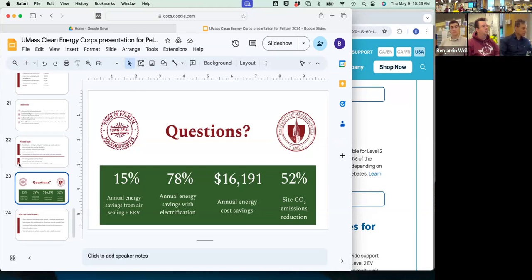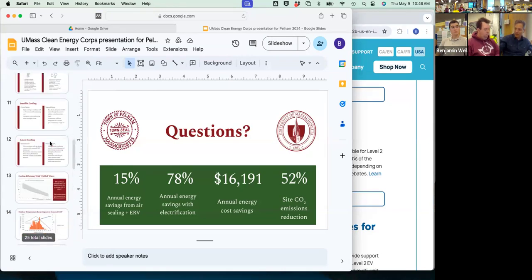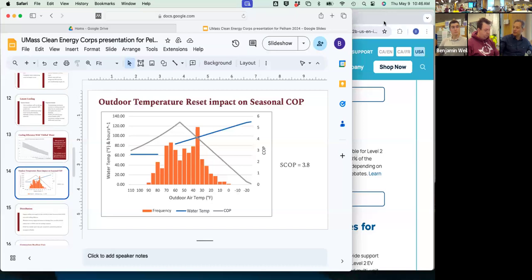The main part is the controls. You want to stay a few degrees above dew point. Fortunately, if we go back to this, it doesn't show the humidity part of it, but it shows that for the frequently experienced temperatures, and this is for a full year, not for the school year, we're typically in here, which means our sensible loads are not terribly high. We have a lot more effort that has to go into dealing with our latent loads, which is why you're so concerned about condensation.